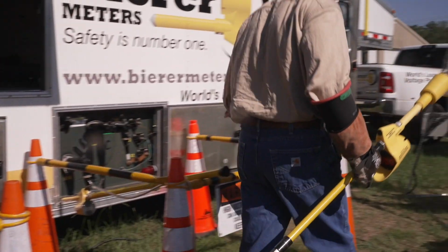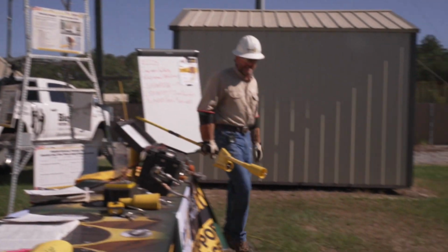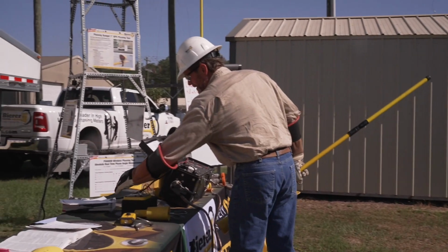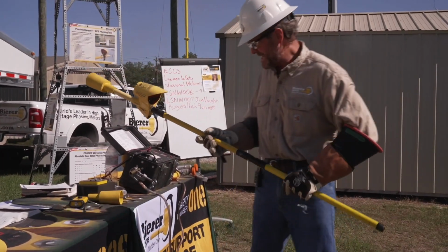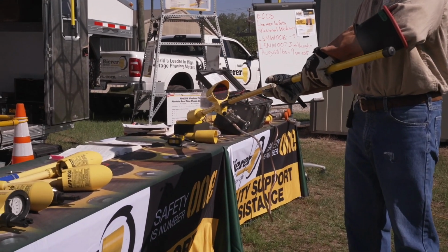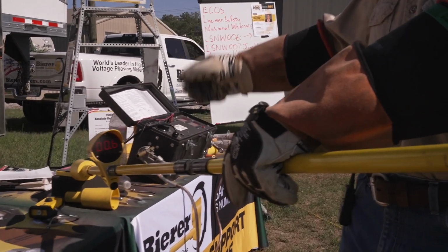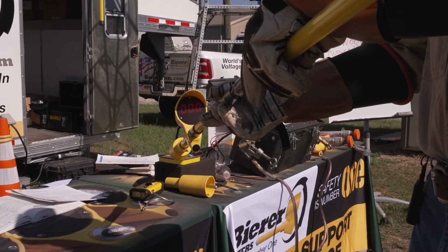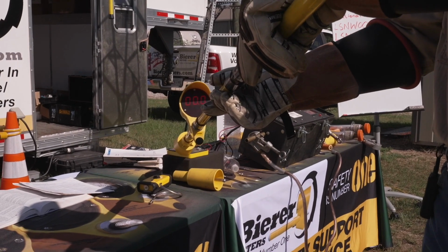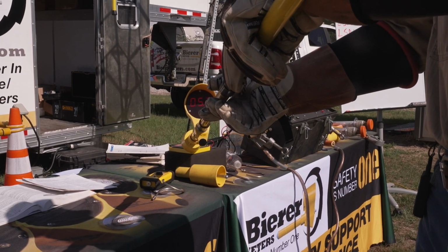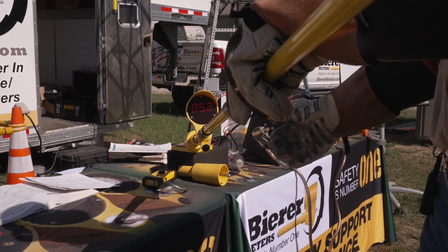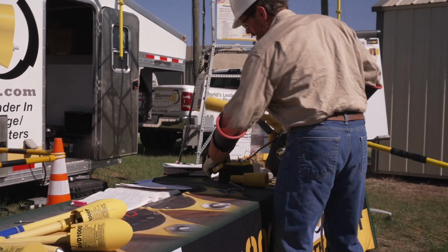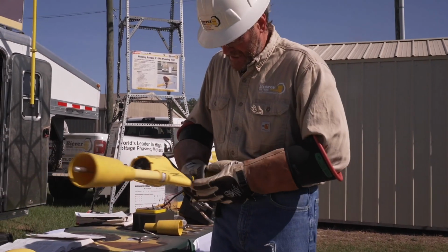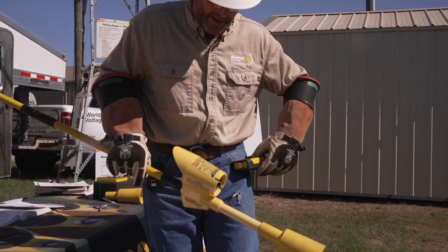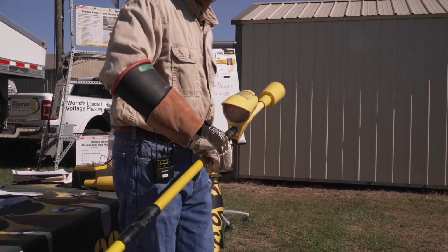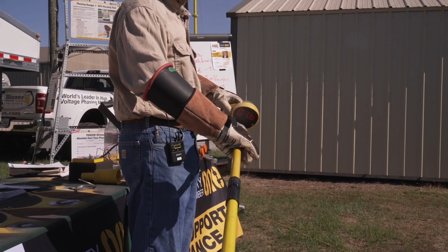Then what we're going to do is test the tester, like a live-dead-live test. We have a 3 kV power supply and you simply test the tester. The testers that have a little hard tip, you want a straight probe usually. There we go, now we know the tester is working. We also have a newer product, a handheld power supply. A lot of utilities are going to this handheld power supply because it's a lot smaller, and they're just adding it to their kits. There you go, test the tester.